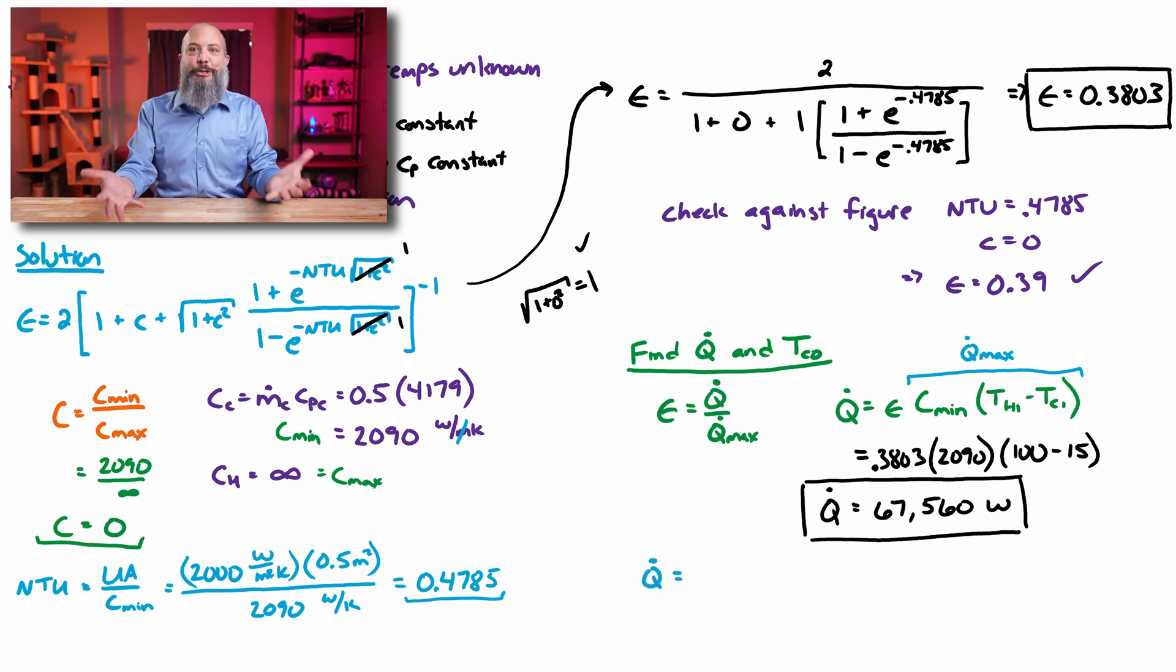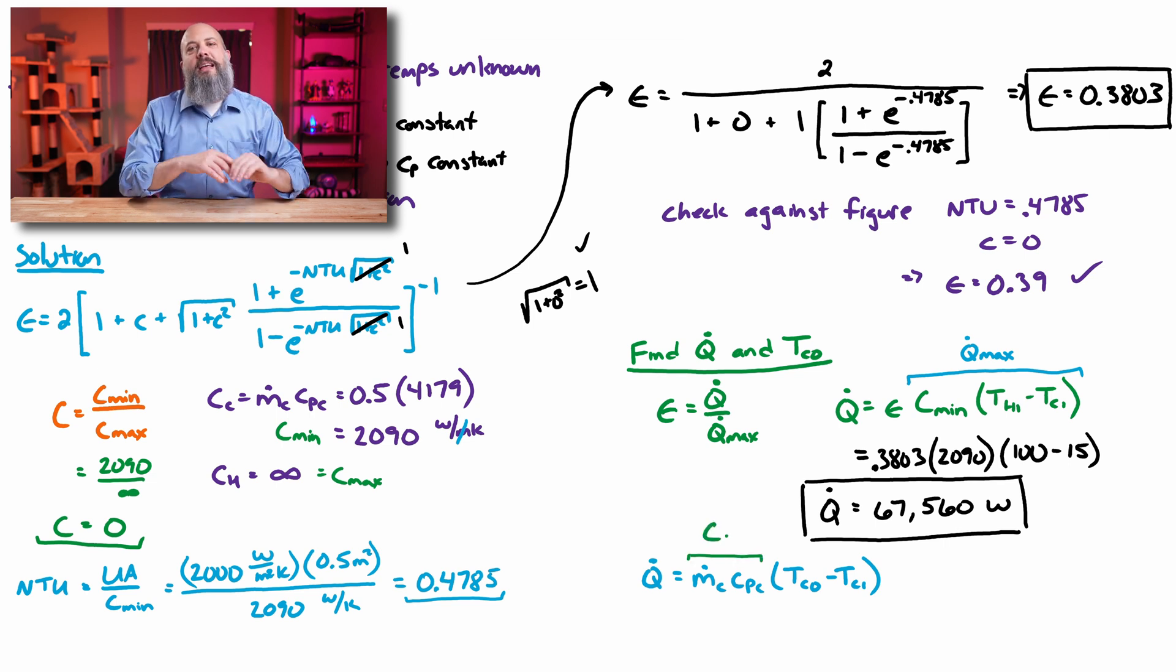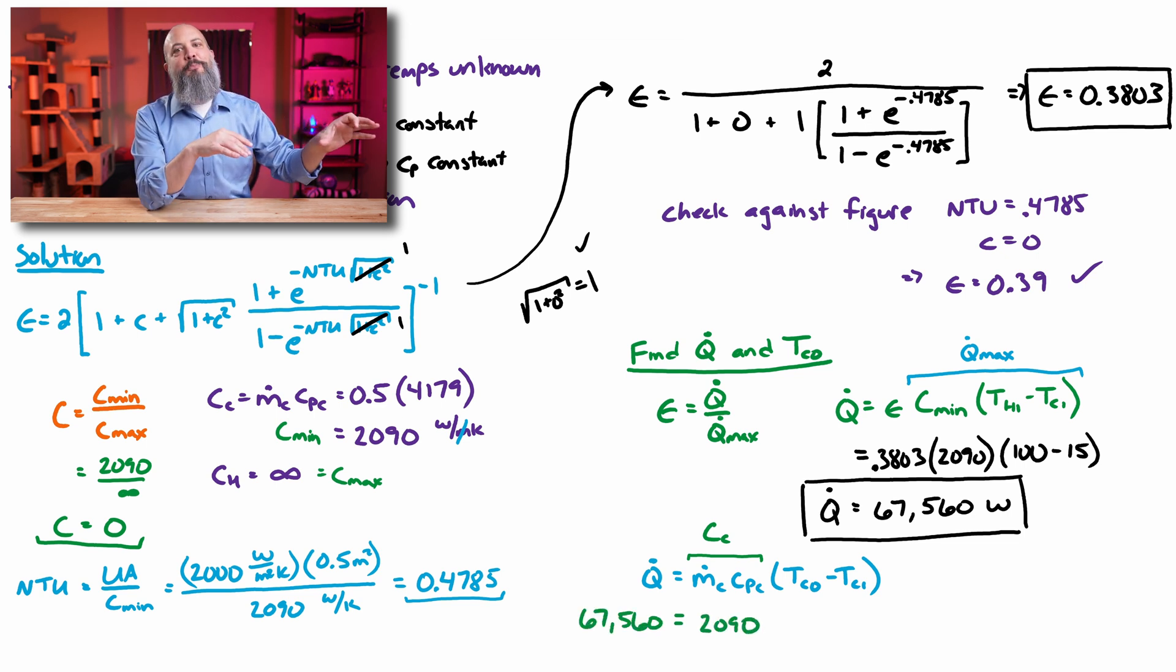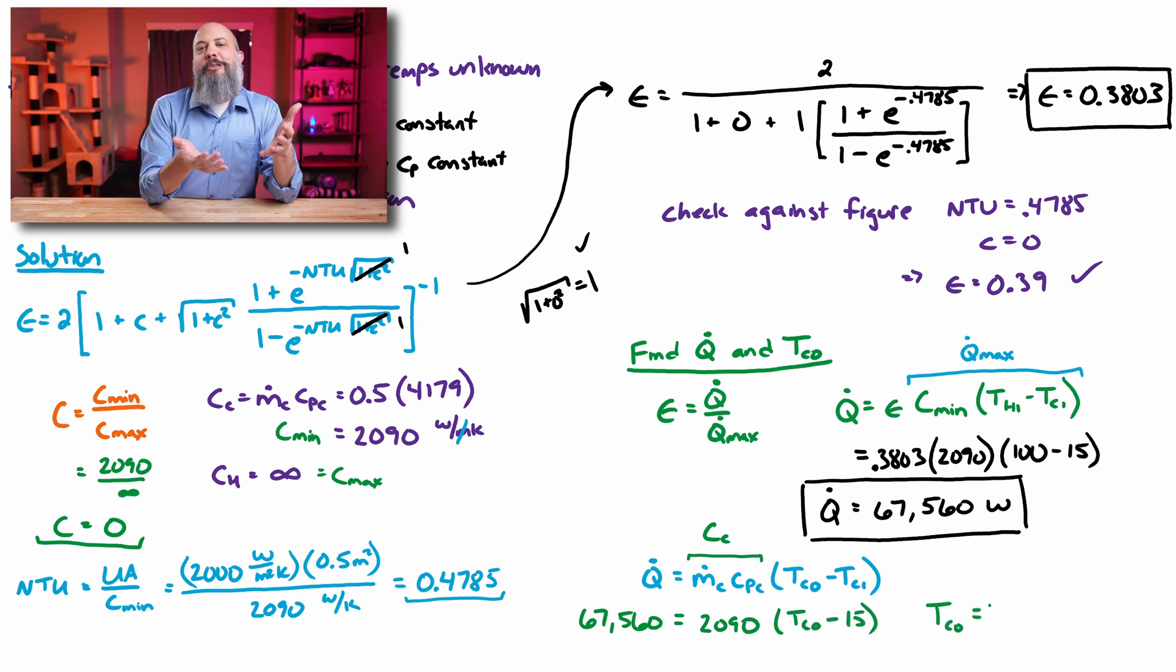This lets us solve for what the final temperature actually is. We have Q dot is M dot CP delta T. We just solved for Q dot, 67,000 watts. M dot CP for the cold flow is 2,090. And then delta T is the actual exit temperature for the cold flow minus the 15 degree inlet temperature. We get an outlet temperature of 47.33 degrees Celsius.